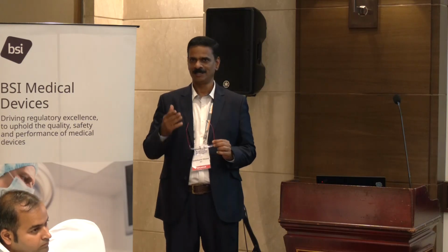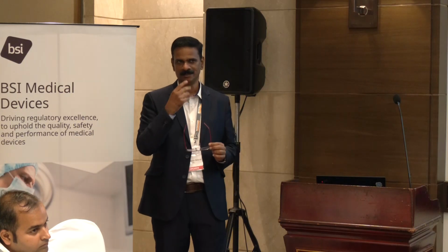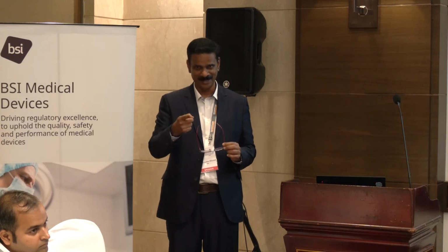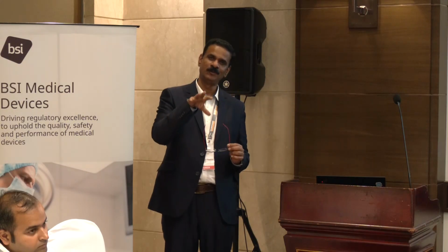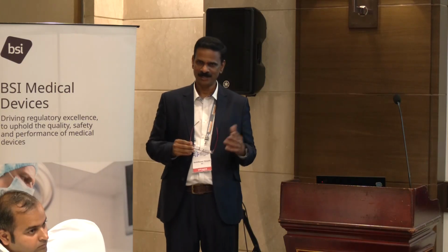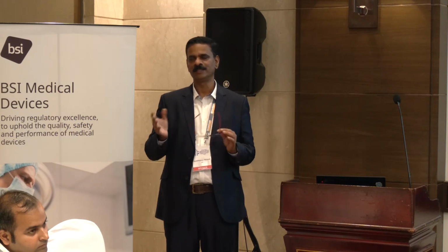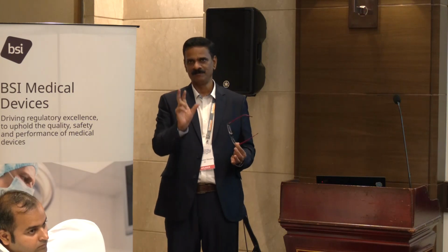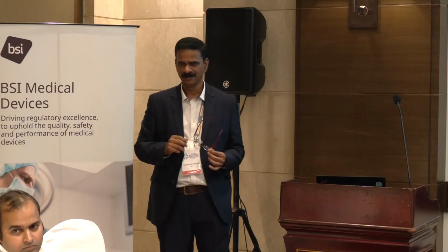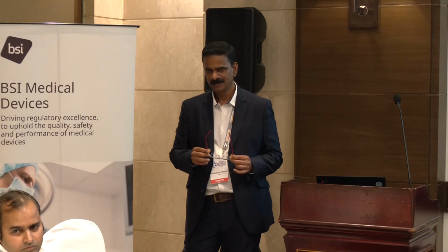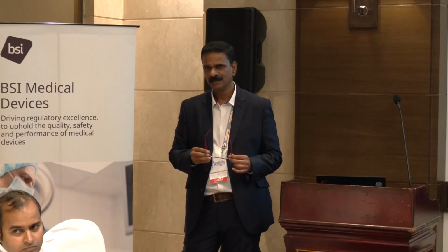But how are you going to claim this? Because the reviewer will go through what changes you made, whether they will affect it or not, and what kind of data you have from your new generation device. Do you have any clinical data at all? No. So you are claiming equivalence with some features added. Earlier it was button type, now it is a display touch screen, and some components were added.